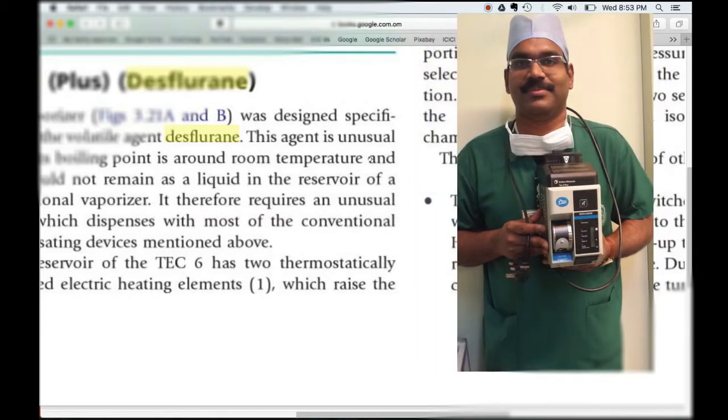We all know that the TEC 6 vaporizer for desflurane is electrically powered, a supplied heat vaporizer. The question is: why is desflurane, which is extremely volatile, heated up to be used as an anesthetic agent?